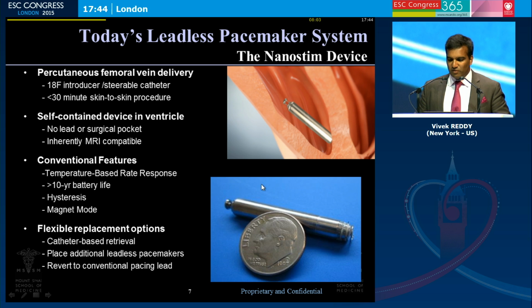The device is fully self-contained, so the battery, the electronics, and the pacing element are all within this particular device. Because there is no lead, at least in theory, this device is inherently MR compatible. It does have many of the features that we see in conventional pacemakers, albeit not all features. It does have the ability to be rate responsive, a battery life that's substantial, and I'll talk more to this, hysteresis and magnet modes. And you can see the back of the device has this nub, which actually can be used to retrieve the device, and I'll show you some data to that.